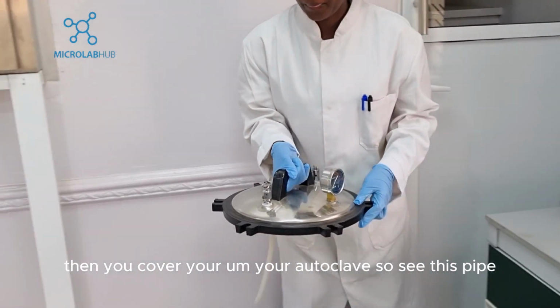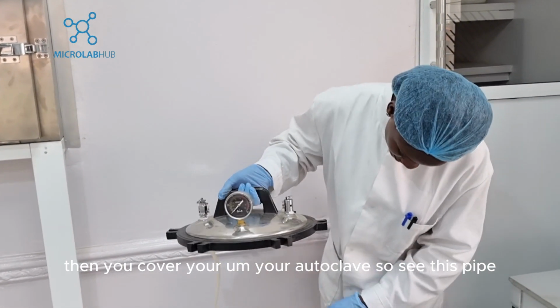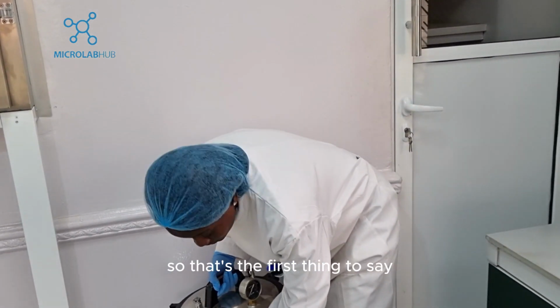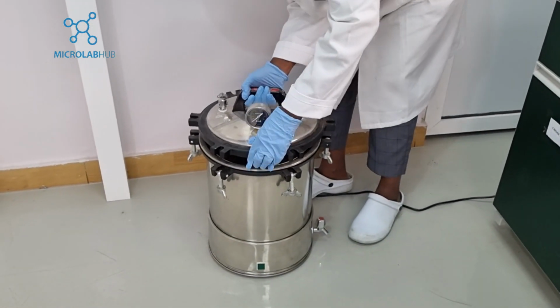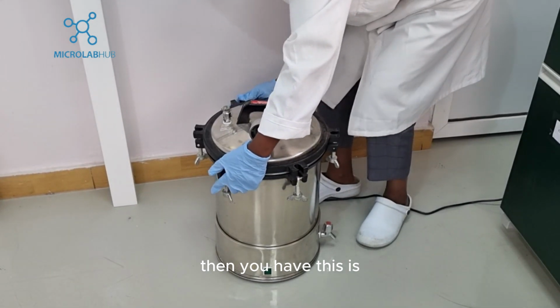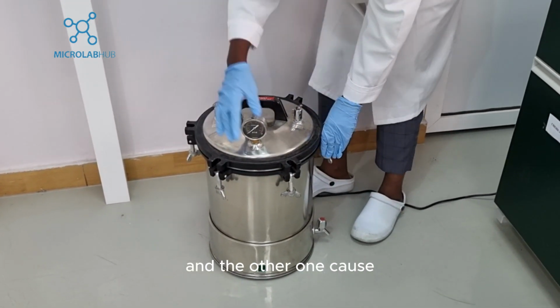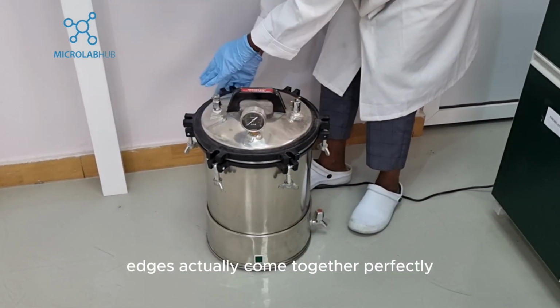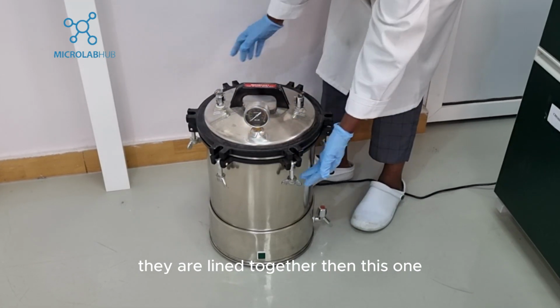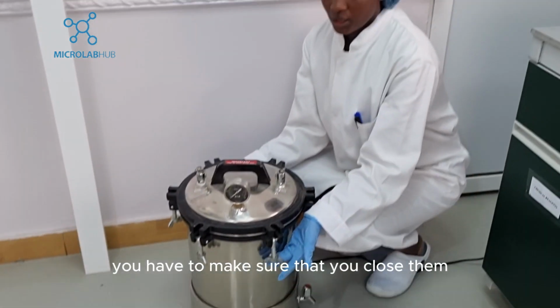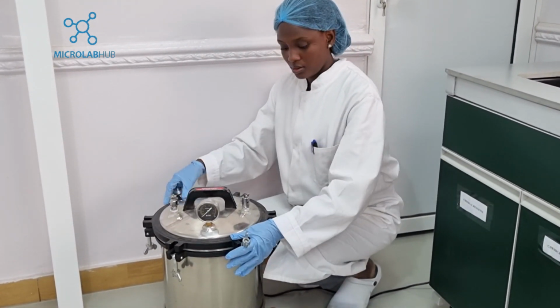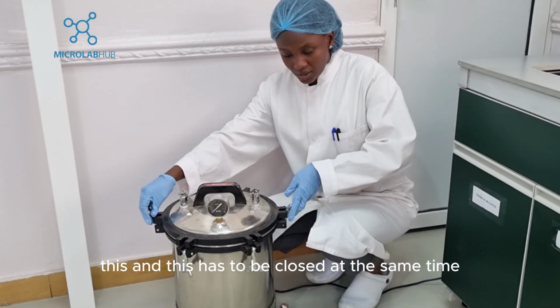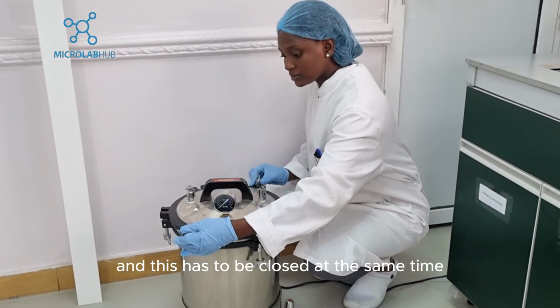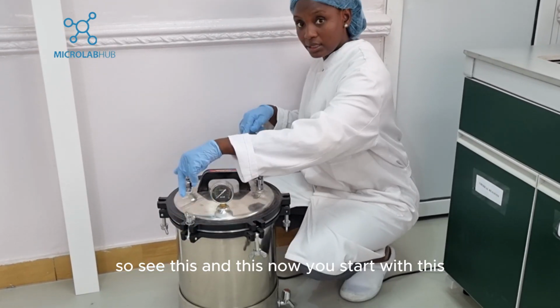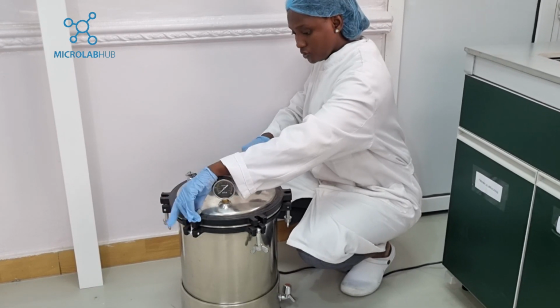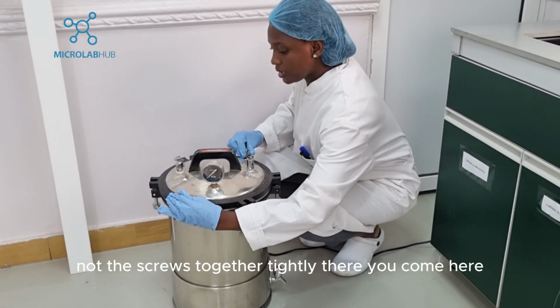Then you cover your autoclave. See this pipe, that's where the steam comes in, so it has to pass through the side. This one is a little bit more technical than the other one, because you have to make sure that these edges come together perfectly. They are aligned together. Then you have to make sure that you close them. This and this have to be closed at the same time, and then this and this have to be closed at the same time. So you screw it together tightly.